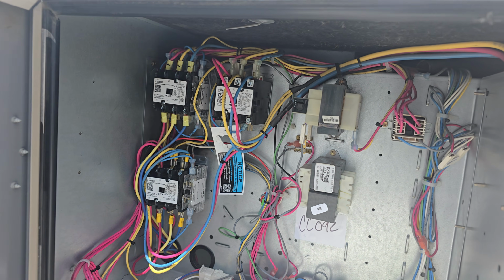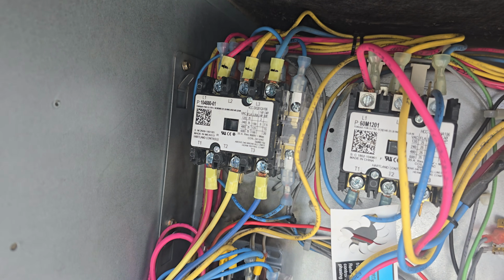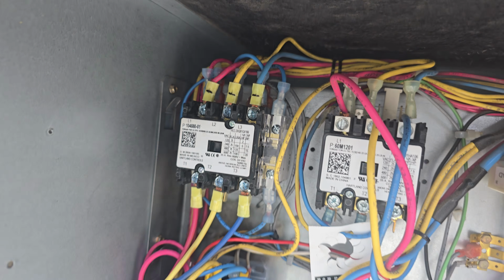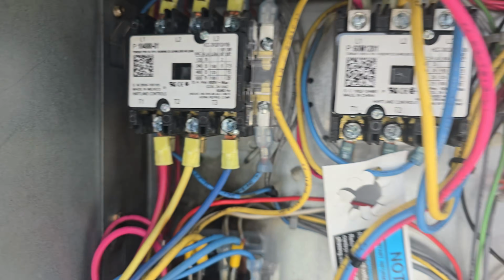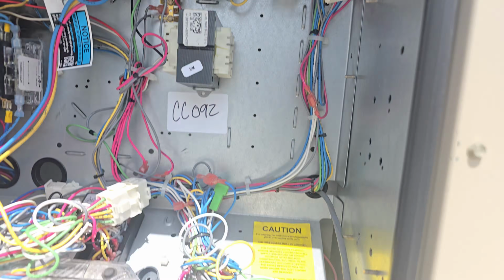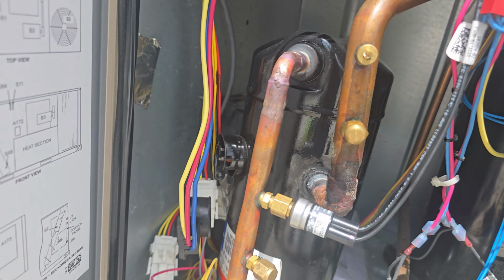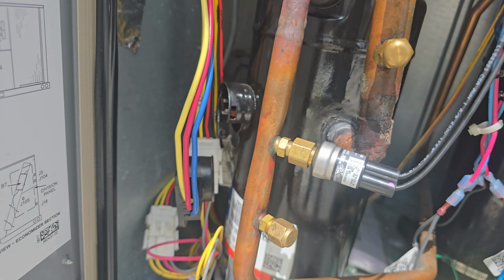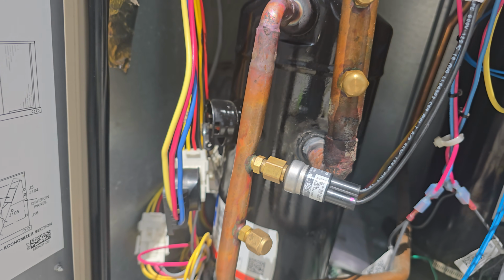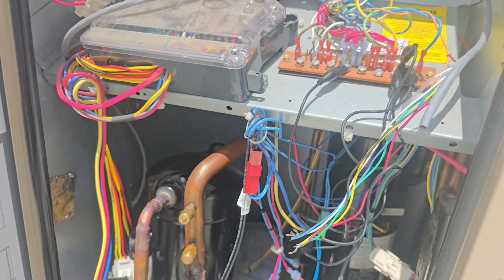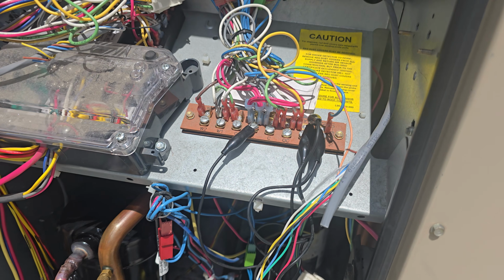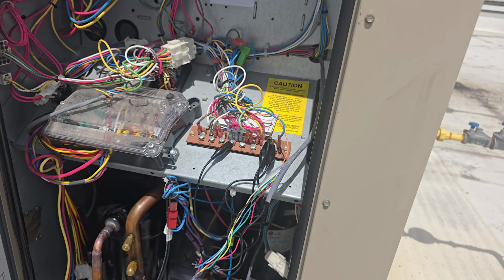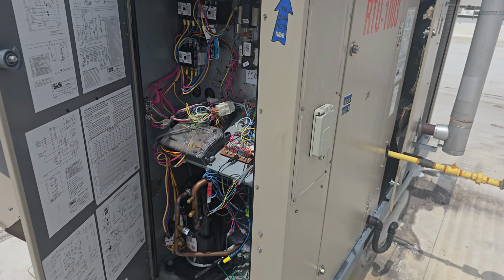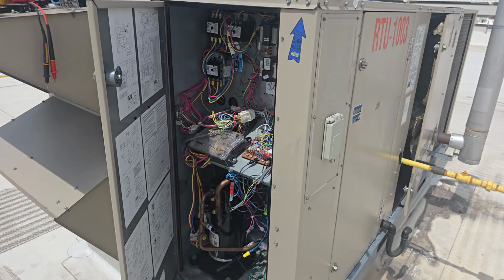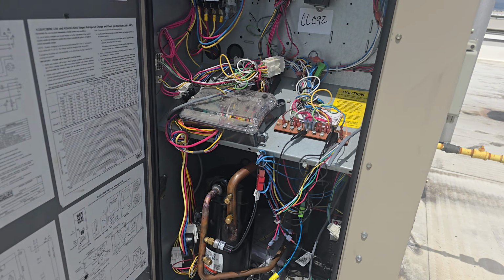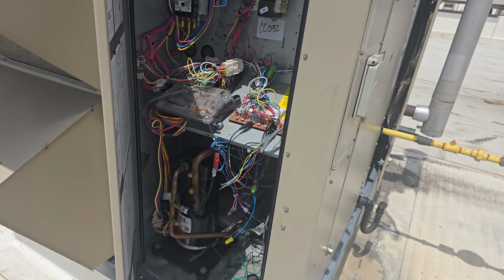Okay, so my unit comes on. Yeah, this contactor that has never closed has closed and remained closed. So two contactors closed, everything is okay. So my unit is running. Again, remember I have not connected my compressor, so I'm going to connect my compressor now, and I will also connect my thermostat wiring, and then we see. So far everything seems to be running fine, and I'm going to update you as soon as I connect my compressor and my thermostat wiring.